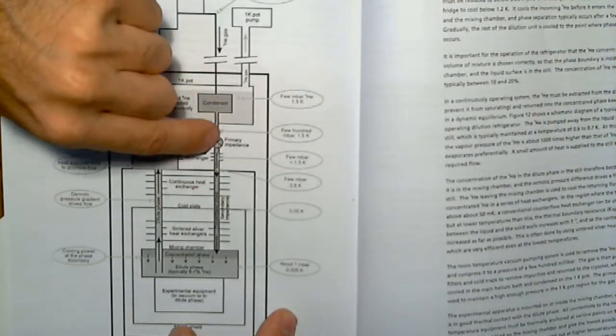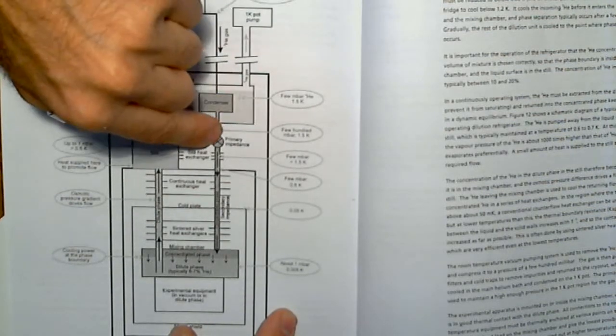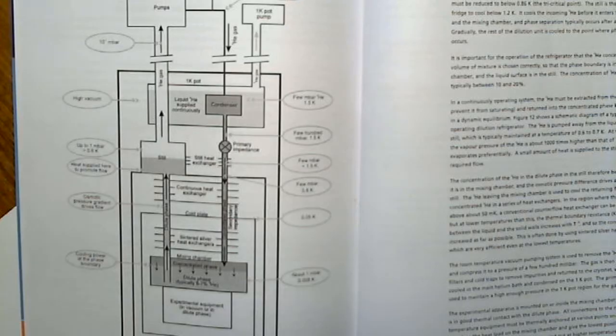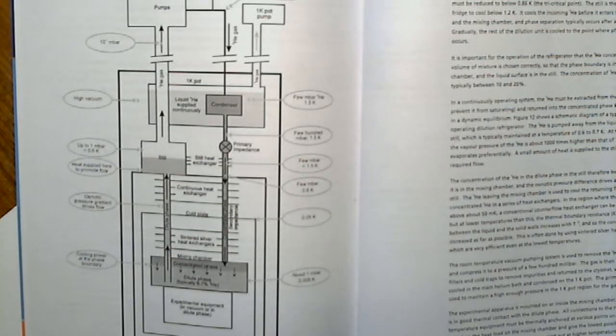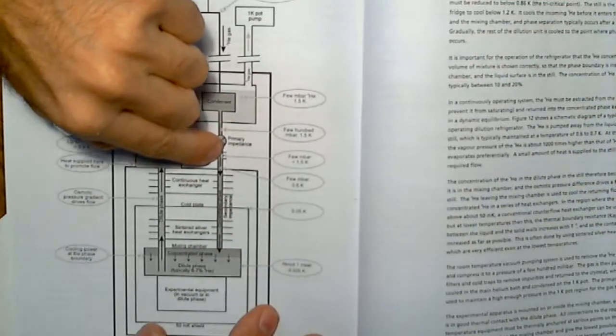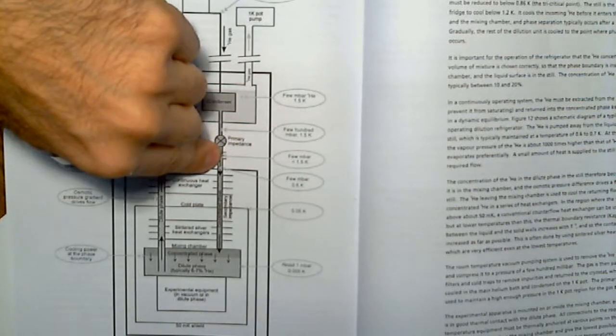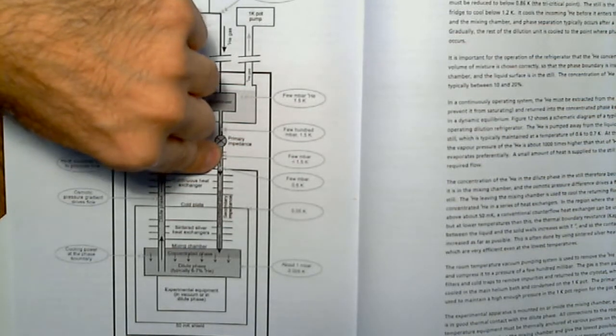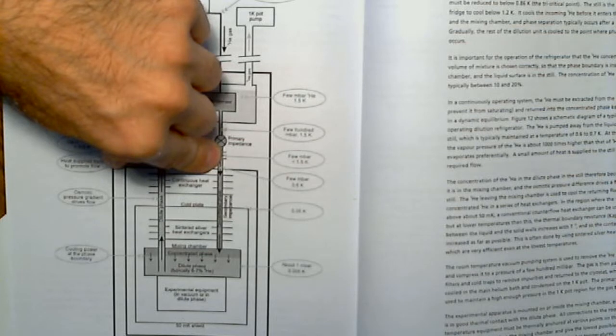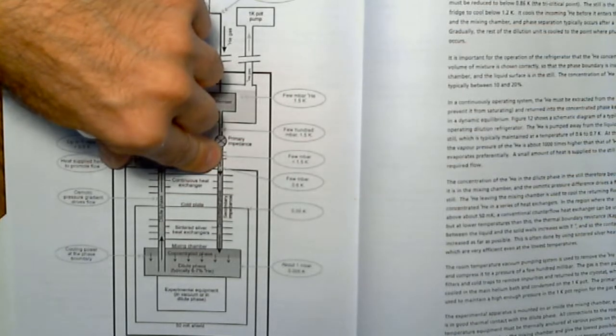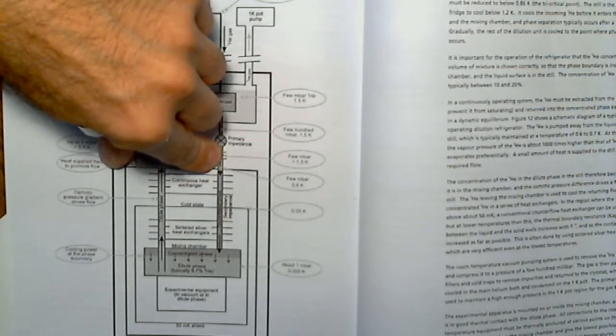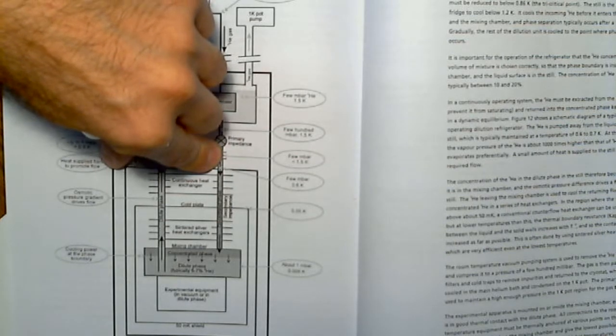After that, once pre-cooled, you have an impedance—a small, very thin restriction. You create pressure on one side, and on the other side liquid comes out; you make an expansion, and after the impedance you get liquid coming out. Of course at the start, at 300 Kelvin, it's not liquid, but the temperature decreases, and normally this circulation from mixture to the impedance really begins below 10 Kelvin.